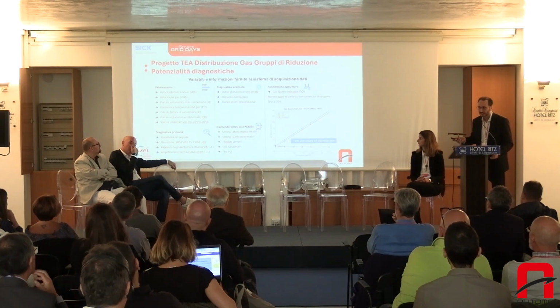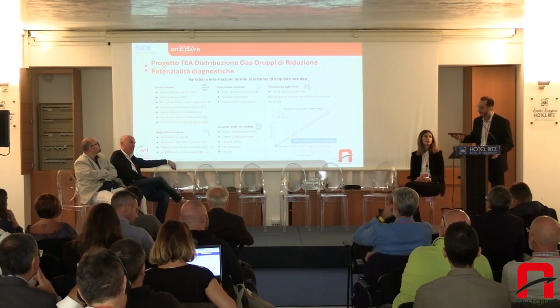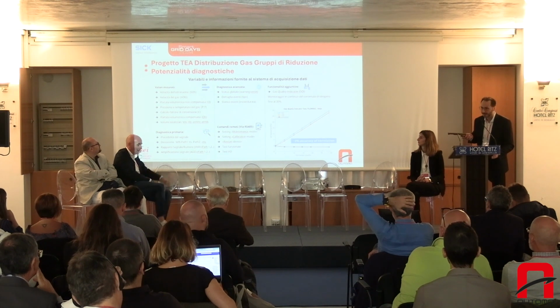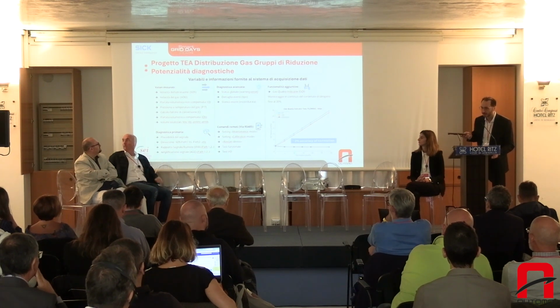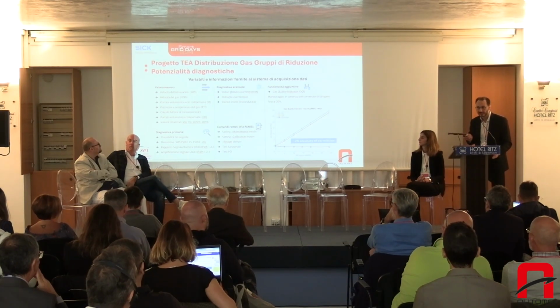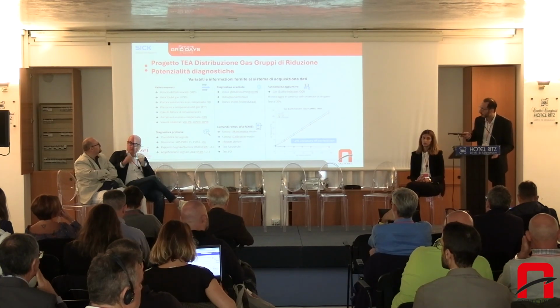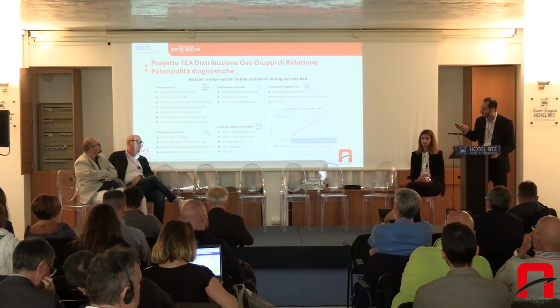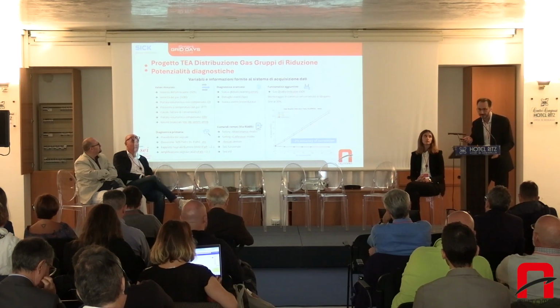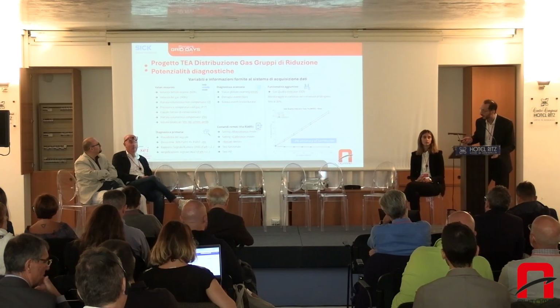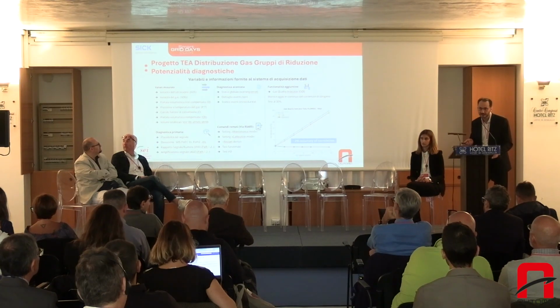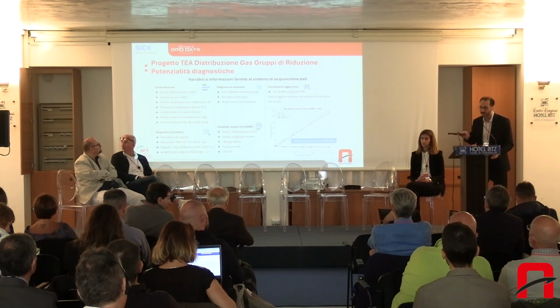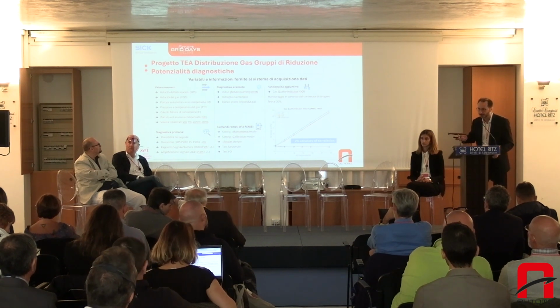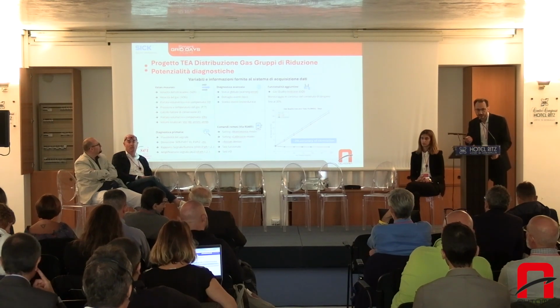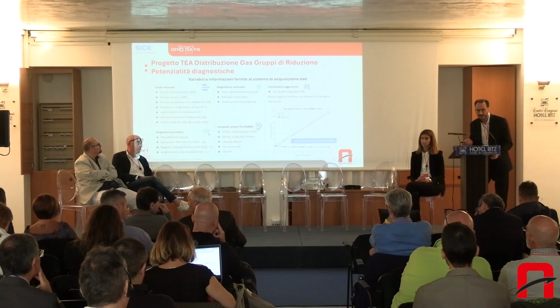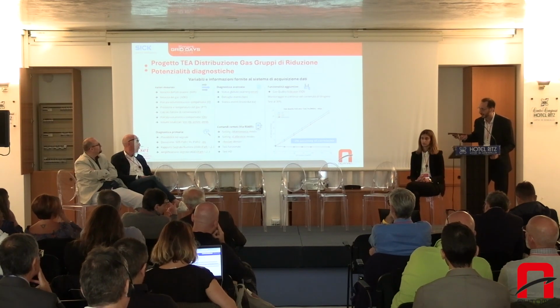We've talked about data. When one talks about data, one has to say that this is an electronic measuring device. So there's a whole series of data that is detected to make the measurement, like the speed of propagation of the ultrasound signal through gas. That's a very important parameter to develop a whole series of diagnostic routine tests. The first piece of data is gas speed, and from it the flow. And by also measuring, for example, temperature, we provide the value in cubic meters. These volumes can then be obtained in conditions of good functioning or in a situation of error or anomaly.